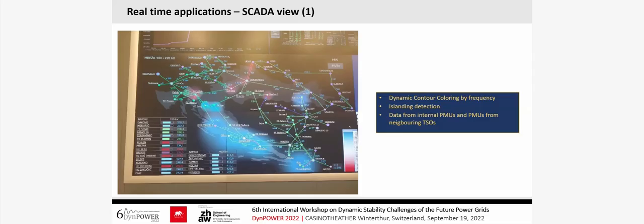What we can see is contour coloring of the frequency. What's important here is how you get that contour coloring. If you use traditional SCADA measurement of frequency, you won't get such a precise value, because you have dead bands and a cycle period for receiving this frequency. But if you use PMU measurement of frequency, you get the exact value, with no dead bands.